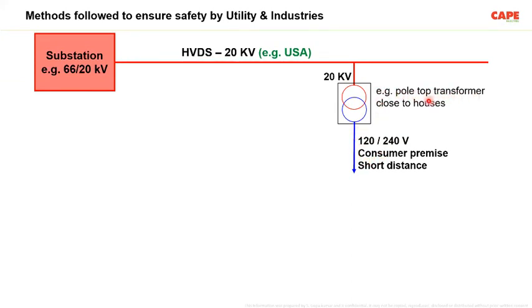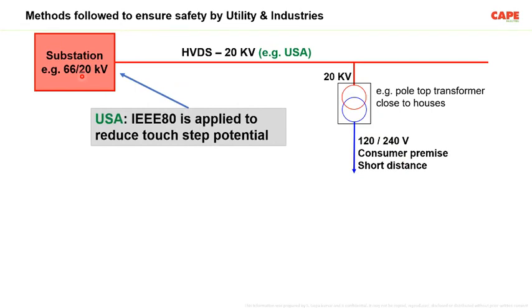And the example, a pole top transformer. Basically, the electricity distribution is happening at 20 kV, and every house or probably a group of houses has a transformer, and the transformer is generally a very small transformer which is connected very close to the load. As a result, the voltage drop at the consumer premise is minimized to a low level. And this 20 kV actually starts from a substation. In this substation, the primary voltage is either 66 kV or even higher, sometimes 132 kV by 20 kV. So according to the American system, the primary voltage of this substation is either 132 kV or 66 kV. Secondary voltage is 20 kV.